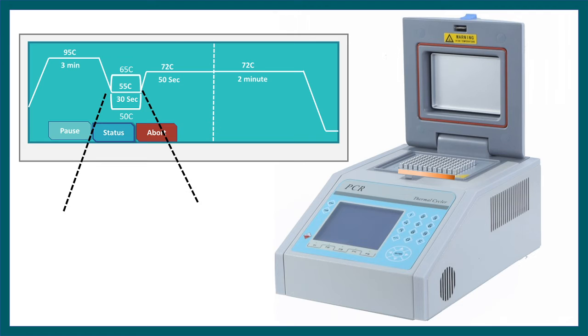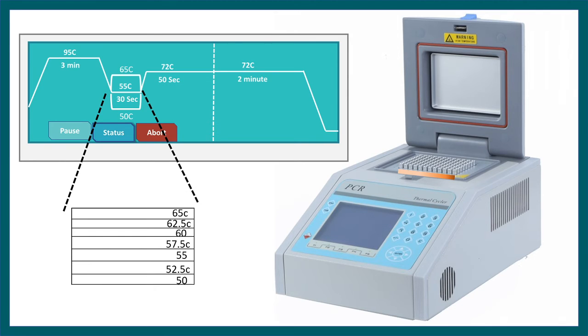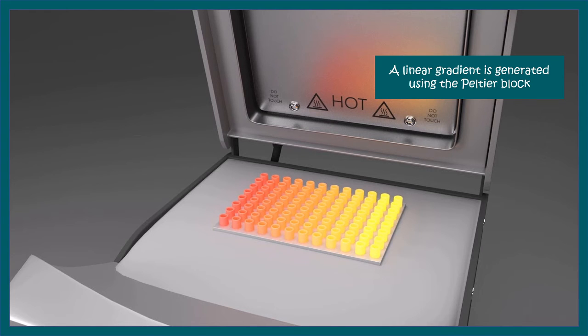So for this example, the cycler would have a temperature range from 50 degrees Celsius to 65 degrees Celsius with an increment of 2.5 degrees Celsius. And this is how the thermal cycler would heat up in this particular step. So instead of one annealing temperature, we are using multiple different annealing temperatures, just to test at which particular temperature primer annealing is optimum and we get a proper amplification which is specific.